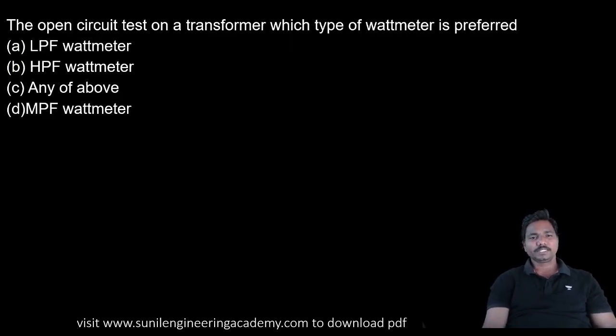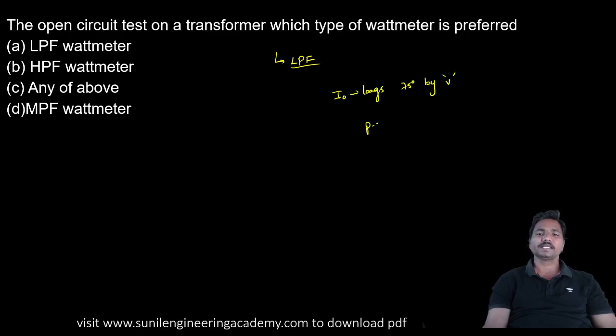In the open circuit test on a transformer, which type of wattmeter is used? Low power factor meter. Why? Because in the case of the open circuit test, the no load test, I naught lags the voltage V by about 75 degrees. So the power factor is low. So a low power factor meter is used. Okay. HPF in the case of the short circuit test.